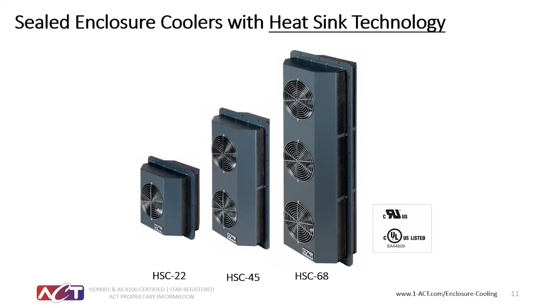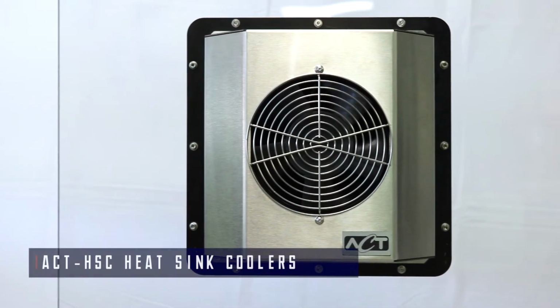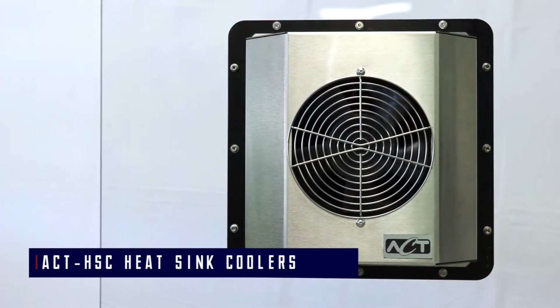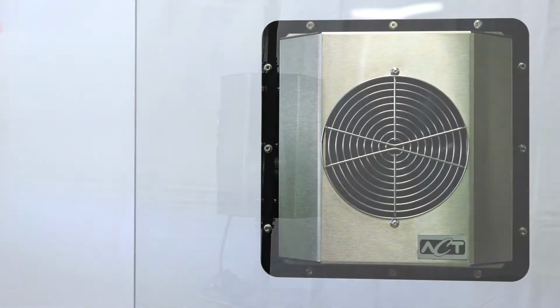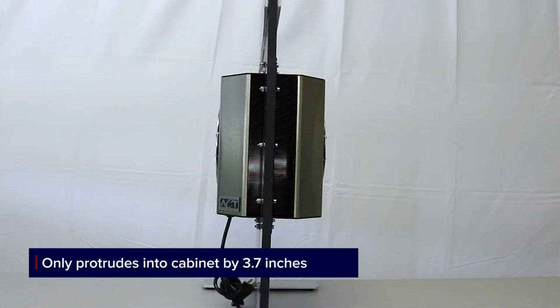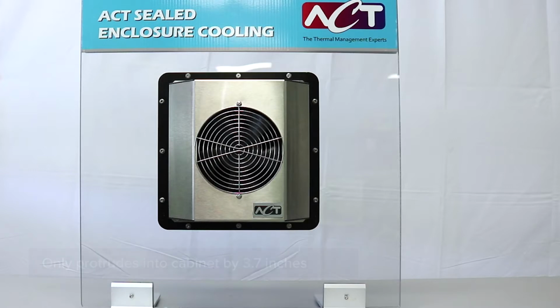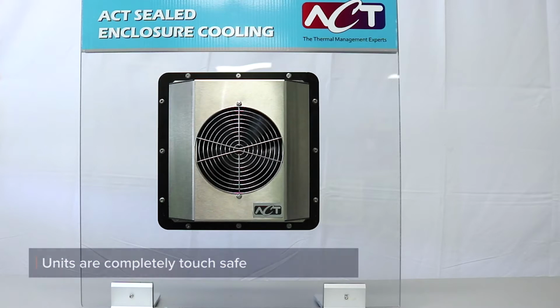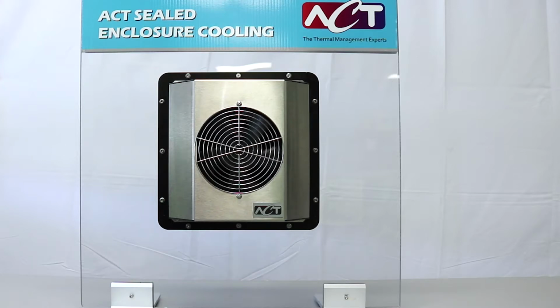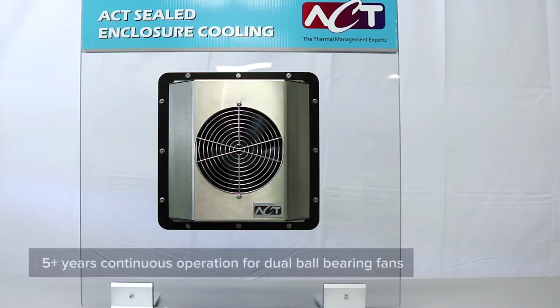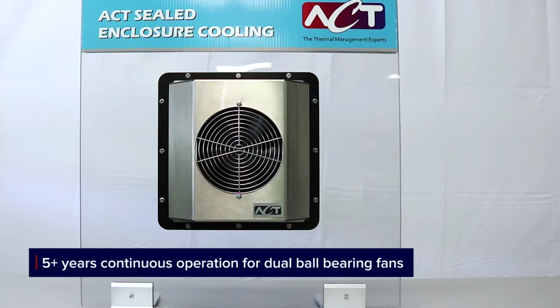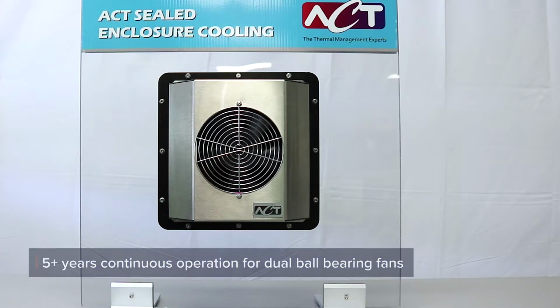They can cool enclosures with heat loads starting at 440 watts to 1360 watts. The ACT HSC is an excellent choice for high component density cabinets. An installed ACT HSC cooler only protrudes into the cabinet by 3.7 inches. The units are completely touch-safe and feature easy mounting and installation. The dual ball bearing fans feature very long life at over 5 years of continuous operation.